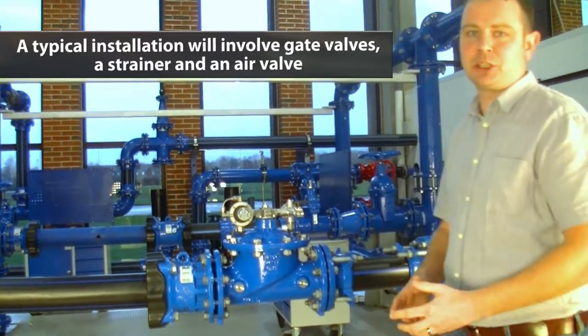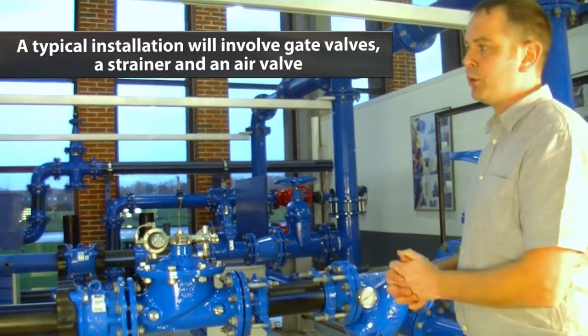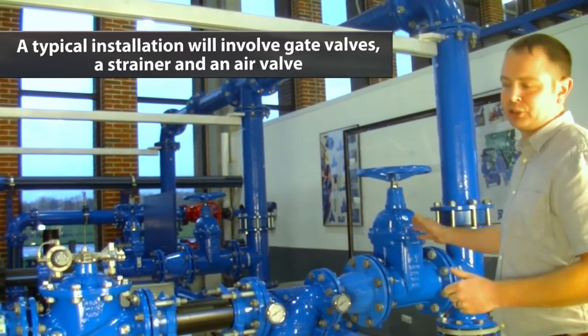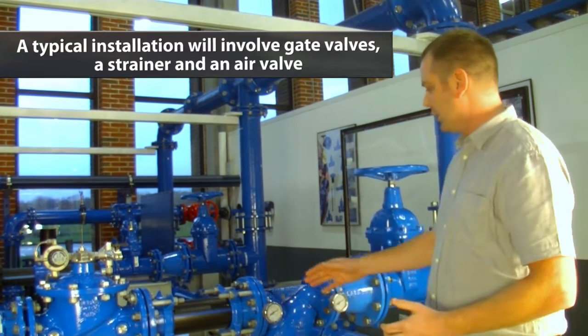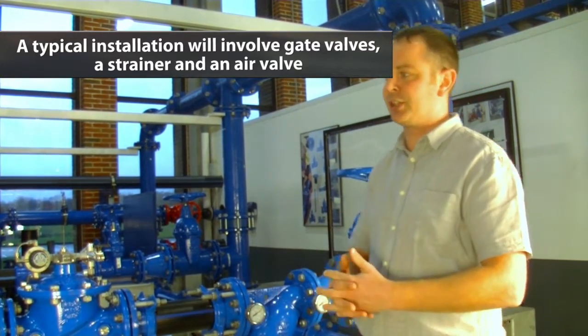The typical installation, particularly of a PRV, would involve isolation valves on site to enable major servicing and maintenance beside the valve body, a strainer, and in most cases an air valve as well.